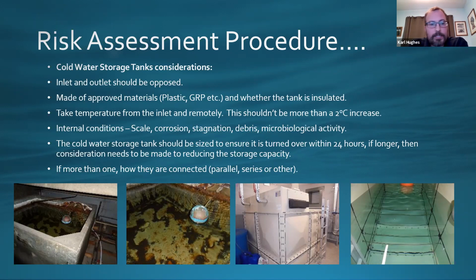The idea of that is that, in roof spaces like the one on the left-hand side there, you're not going to get a lot of heat gain from the ambient temperature in the roof space into the water. You take a temperature from the inlet and the outlet. The idea is you're making sure you're getting a good cross flow of water through the tank itself. There shouldn't be any more than a 2-degree difference between the incoming main at the ball valve and the cold water storage tank temperature remote from that.